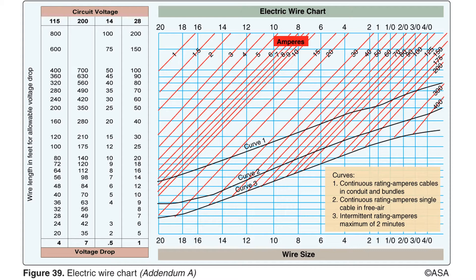We want to select wire with a gauge or length with a low enough resistance to prevent the circuit from overheating, without using an unnecessarily large gauge wire, because heavier gauge wires take up space, add unnecessary weight, and increase cost. The problems we will work in this class will all involve the 28 volt circuit with a maximum allowable voltage drop of 1 volt.